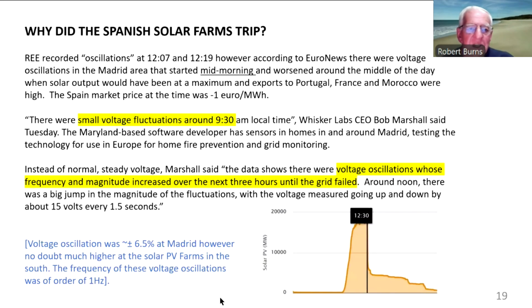Well, why did the Spanish solar farms trip? That's the key. Why did they trip in the first place? And as you saw earlier, Red Electrica recorded some oscillations at 12:07 and 12:19. However, there were voltage oscillations in the Madrid area that started mid-morning and worsened around the middle of the day when, of course, the solar output was at maximum, and so were exports to Portugal, France and Morocco.